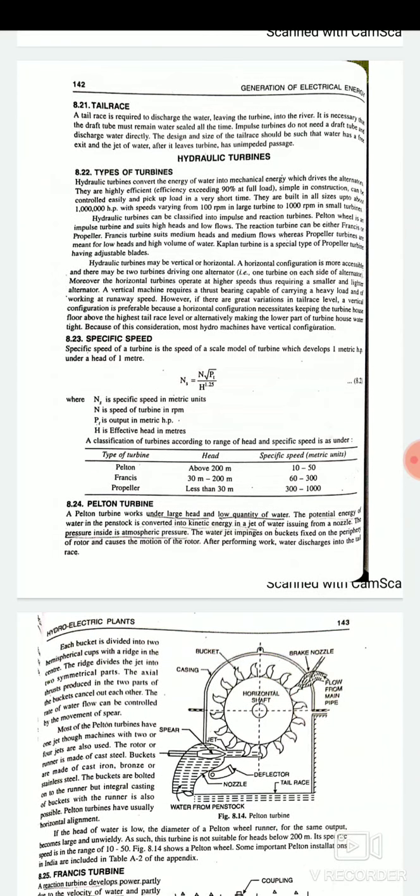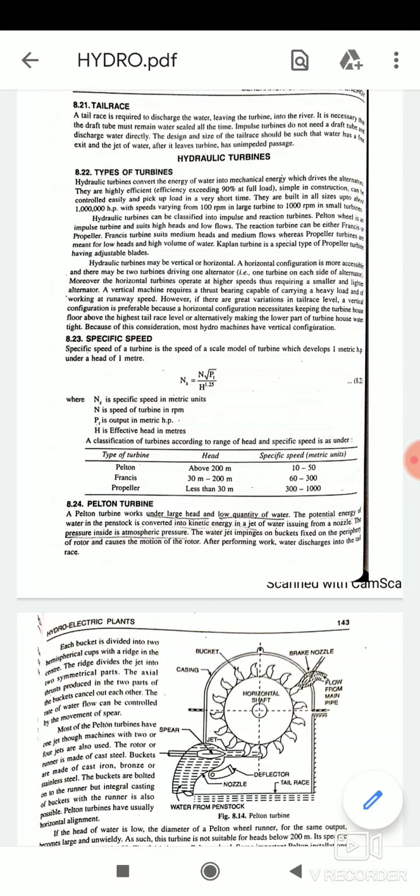First is types of turbines. As we know there are three types of turbines we use: Francis turbines, Kaplan turbines, and Pelton turbines. The hydraulic turbines convert the energy of water into the mechanical energy which drives the alternators. So this is the main function of the turbines which converts water into mechanical energy, and then mechanical energy can be used for the driving of the alternators which produce the electricity. The hydraulic turbines are the very important part of a hydroelectric power plants. They are highly efficient. Efficiency must be exceeding 90% at the full load. Simple in construction and can be controlled easily and pick up load in a very short time. They are built in all sizes up to 10 lakh HP with speeds varying from 100 RPM in large turbines to 1000 RPM in small turbines.